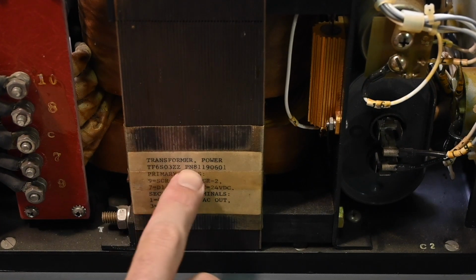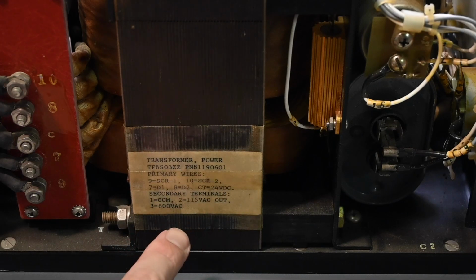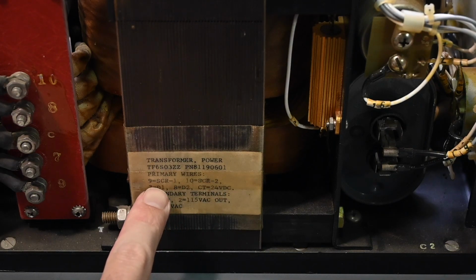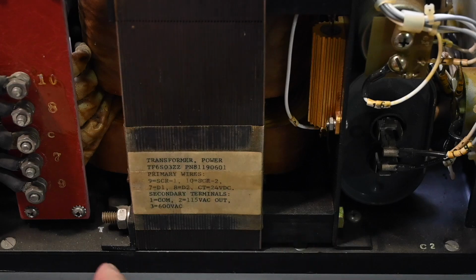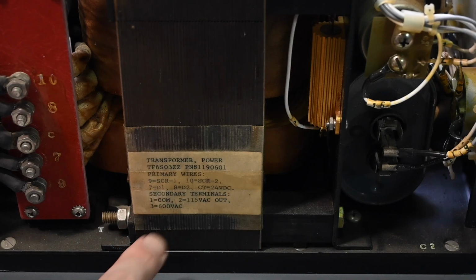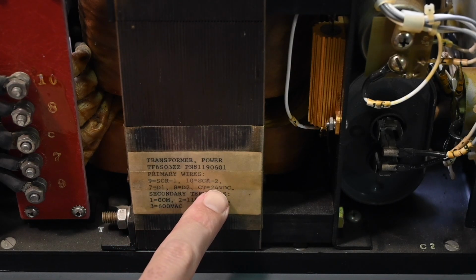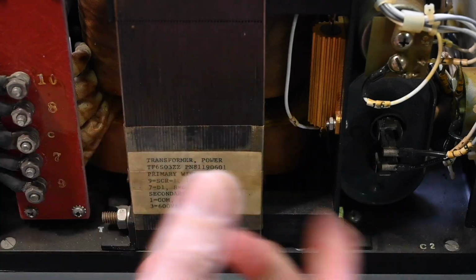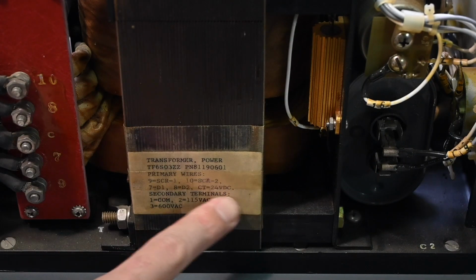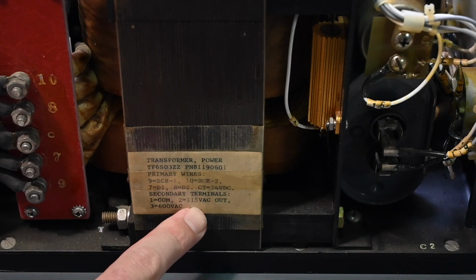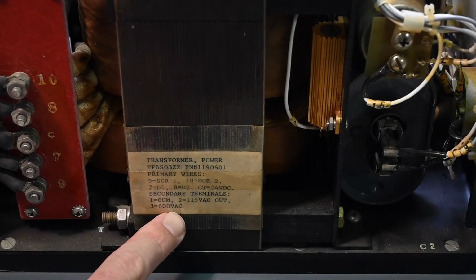So: transformer power, some part numbers it looks like, and then it says primary wires, SCR1 and SCR2. Yeah, so there are two SCRs. There's a diode D1, D2, center tap, 24 volts DC. So they're bringing the voltage into the center tap and then switching both sides of the transformer. Then secondary terminals: 1 is common, 2 is 115 volts out, and 3 is 600 volts.